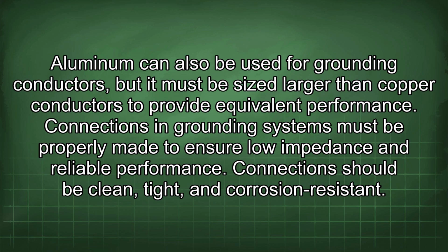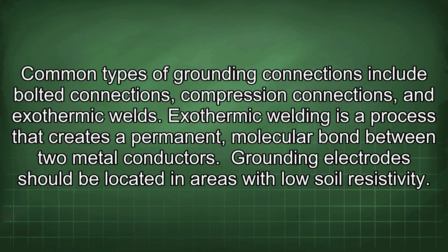Connections should be clean, tight, and corrosion resistant. Common types of grounding connections include bolted connections, compression connections, and exothermic welds. Exothermic welding is a process that creates a permanent, molecular bond between two metal conductors.